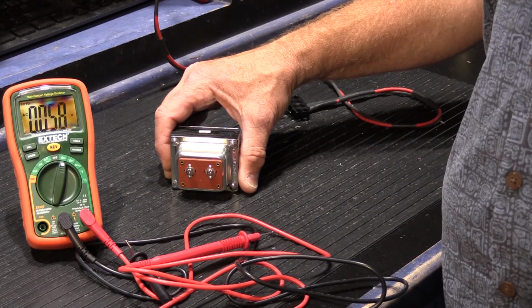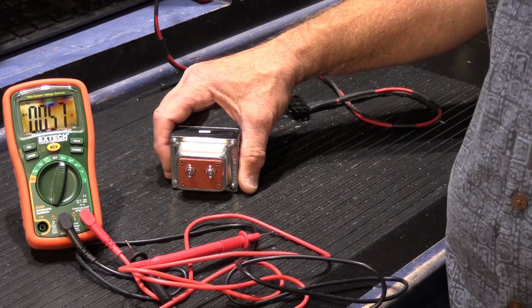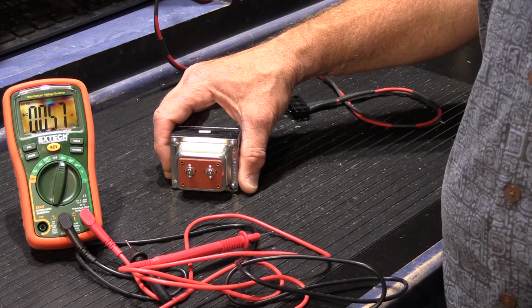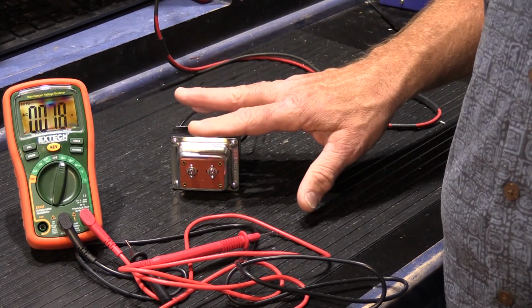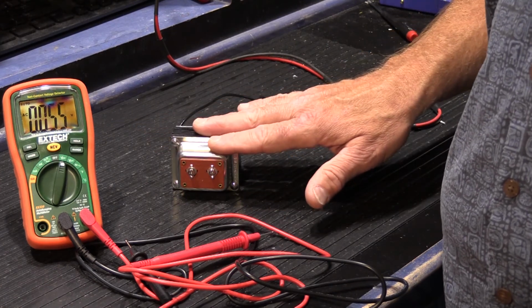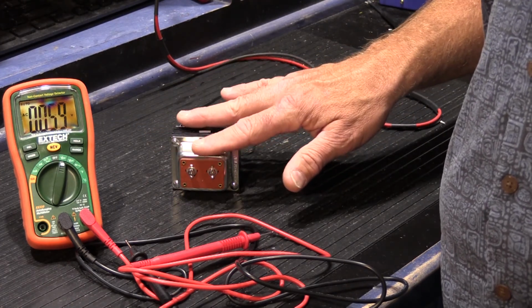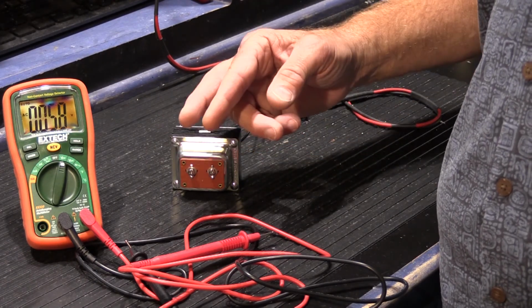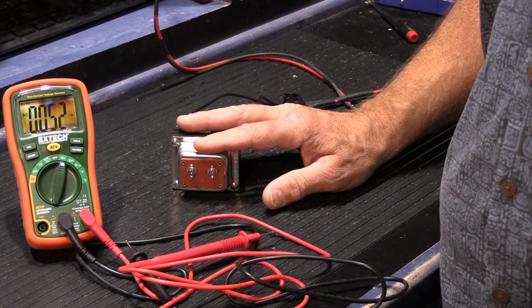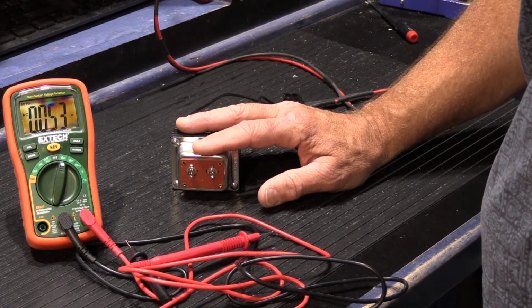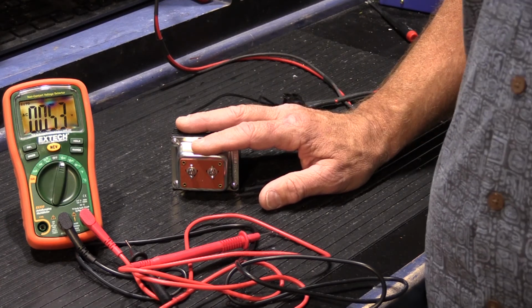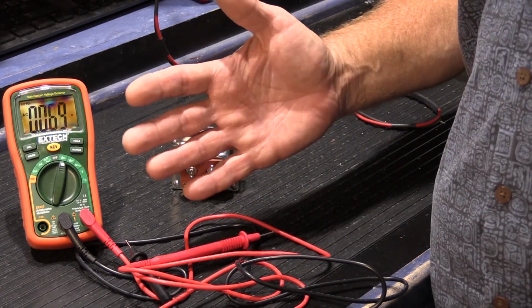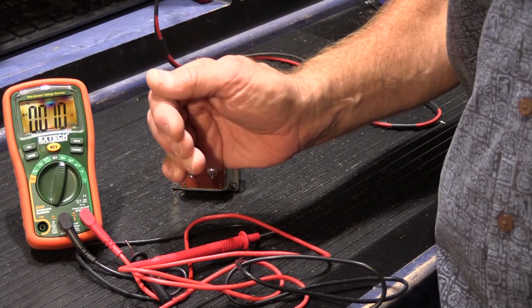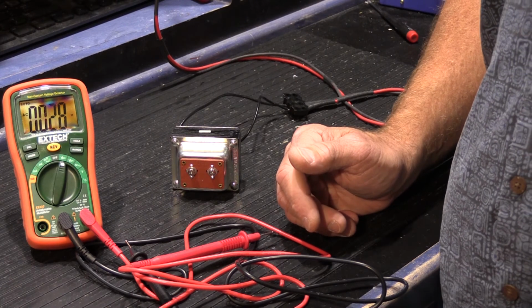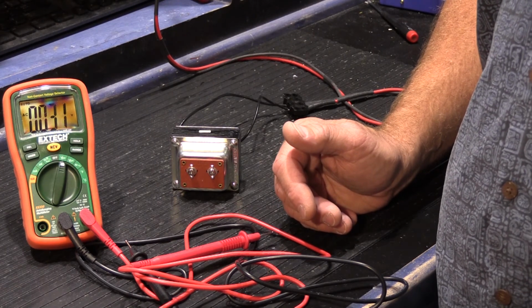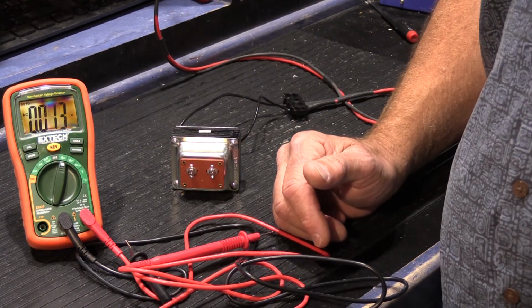If a transformer has been hot for a really long time, months and months or years and years sometimes, the enamel on the windings inside the primary and secondary side, which is the insulation that keeps the little copper wires in the windings from actually touching each other, will start to break down and become a very poor insulator. It's as if someone took all those windings, which were originally all separated by the enamel, and crammed them all together as tightly as they possibly could. So they're not exactly all touching each other, but they're more touching each other than when it was brand new and the enamel was in good shape.